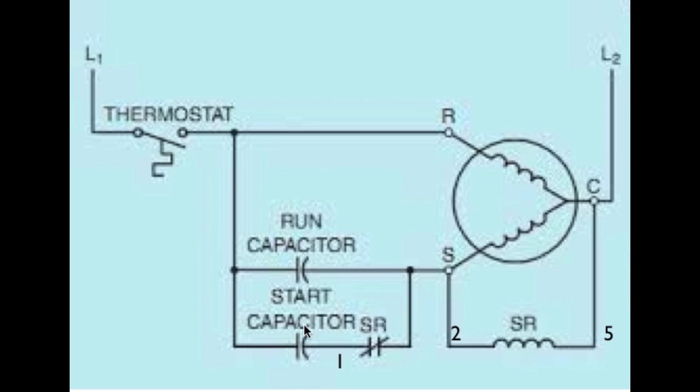Start capacitor. Now I've noted down here a 1, a 2, and a 5. Those are the three terminals of the potential relay that are hooked into this. So terminal 5 goes to common, terminal 2 goes to start.